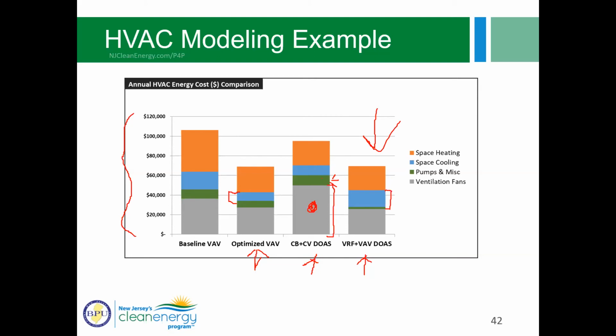And real quickly before I leave this slide, the other thing I found interesting was just the heating energy consumption, or not energy consumption, but cost between the optimized VAV, so this orange here, and the VRF. The VRF is slightly lower, and I think that's only because, to remind you, the optimized VAV had condensing boilers, and then the VRF obviously has VRF for heating. And while with VRF the heating EUI, site energy, is probably very low compared to the condensing boilers, because electricity is more expensive than natural gas, you don't see quite as much savings as maybe you would think using such a high efficiency heating system. So that's an interesting piece as well.